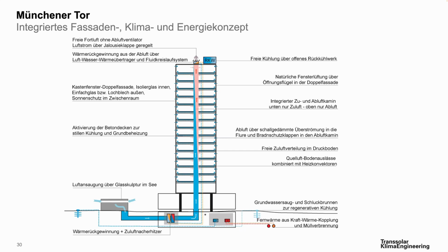Then we had the problem of heat recovery. So we put a little heat exchanger on top here. It's an air to water heat exchanger. We extract the heat from the exhaust air and pump it with the fluid system back to the basement. We have another system like this, and then preheat the incoming air. So we don't bring the air back, because that needs large shafts. We just use some water pipes to bring the heat back. Then we have an earth duct in the ground to precondition the air. We have a little heat exchanger connected to the district heating system, and that's about it.